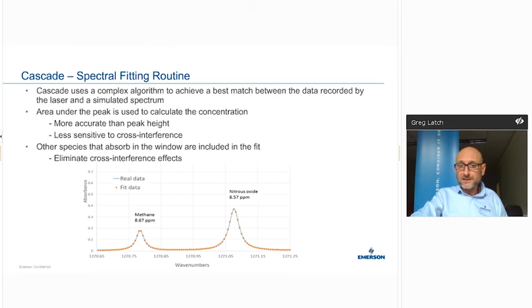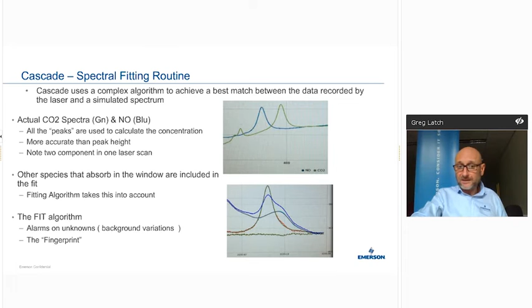Just a quick one, it shows you an example of a single analysis. We're using CO2 spectra on the top right-hand graph, and NO in blue. You can see, for example, we can pick up 2 components of interest in the one laser scan. We can do multiples depending on the amount of lasers embedded within the analyzer in its own right as well. And then, for example, on that bottom right-hand unit, if there is a gas or a background variation for something that we weren't told of or didn't account for, we can actually see that, and then we can engineer around that. So if there is a gotcha moment that might come into play, we can definitely manage around that, and it's quite easily done, believe it or not, as well. And it's based on the fingerprinting of our fitting program and algorithm.